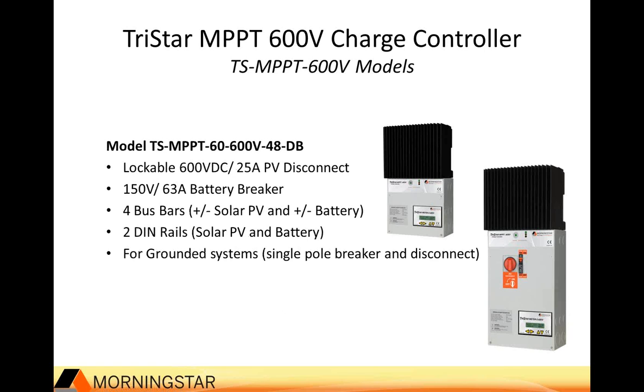Then what we offer is on the disconnect box version, we give you the following additional features. First is a lockable 600 volt DC 25 amp PV disconnect, so that's included. We give you a 150 volt 63 amp battery breaker, so that's both a disconnect and a circuit breaker design as well, included in the controller. There are 4 bus bars inside for both the positive and negative of the solar PV and the battery, so you have several landing points for your wiring. There are 2 DIN rails inside as well that give you the option of maybe reconfiguring the hardware, or in some cases if you had 2 strings and you wanted to add a fuse holder, you could do that as well. And this is all designed for grounded systems, so we give you a single pole breaker and disconnect, and that could be used in either a positive or a negative ground configuration.